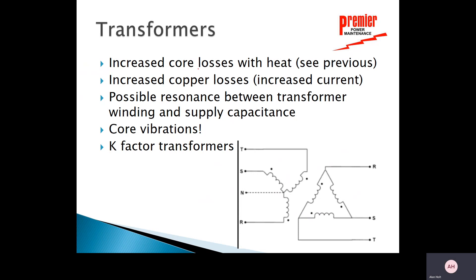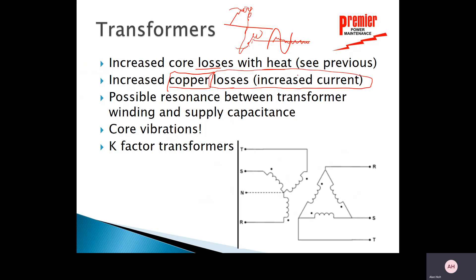In transformers we see increased losses from heat — the same as in generators — and also increased copper losses. I've got my sinusoidal waveform at 60 Hz, but there's other garbage riding on there too. Those additional harmonic components increase the current (since higher voltage creates higher current), and that increased current creates I²R losses — watts lost as heat.